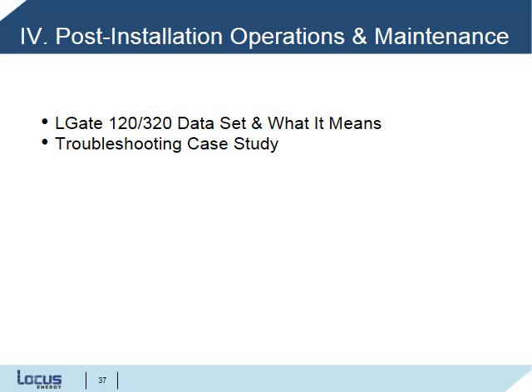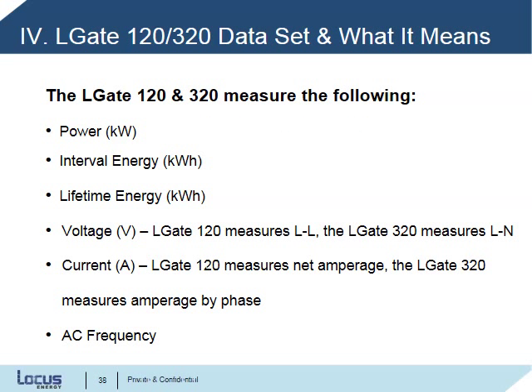Now that we've gone over basic installation and best practices, we'll go over a few considerations for post-installation operations and maintenance. We'll go over the LGate 120 and 320 dataset and provide a troubleshooting case study to bring it all together. As I mentioned earlier, the LGate 120 and 320 will measure the following: power, interval energy, and lifetime energy. The LGate 120 will measure line-to-line voltage, and the LGate 320 will measure line-to-neutral voltage. The LGate 120 measures net amperage, while the 320 measures amperage by phase. Both meters will measure AC frequency.